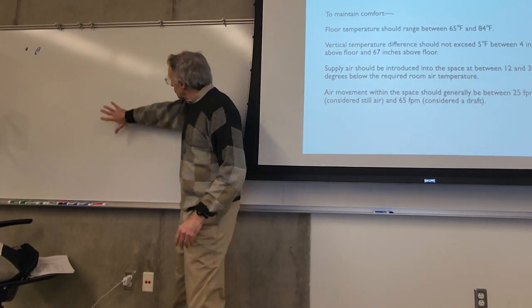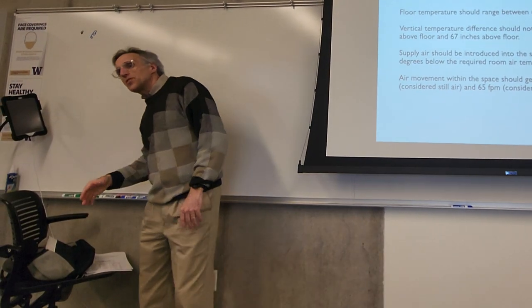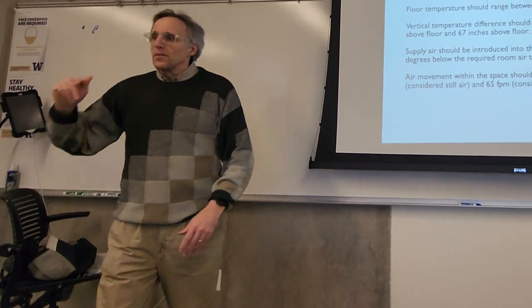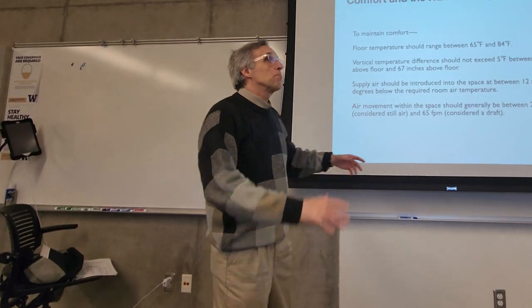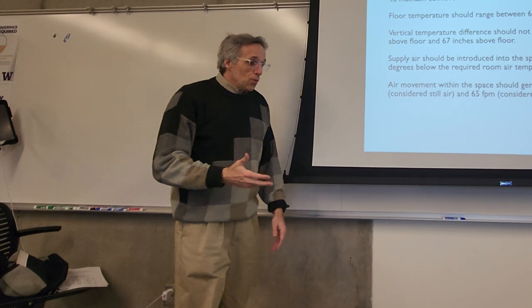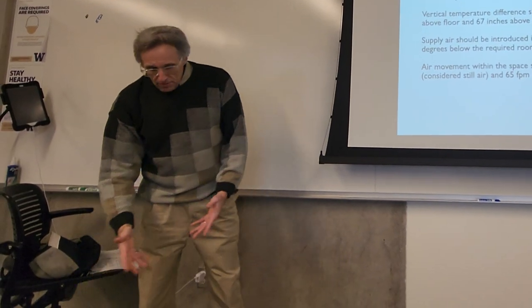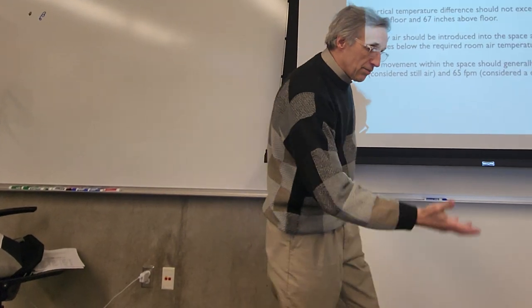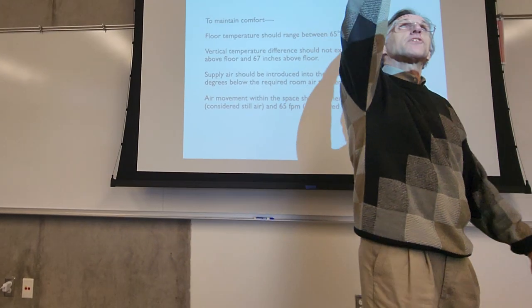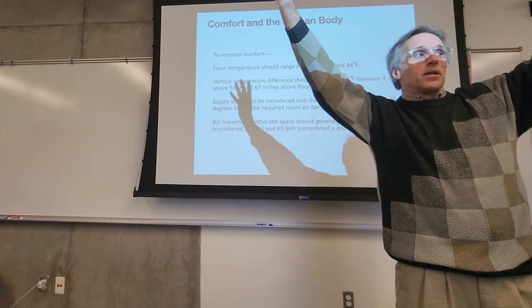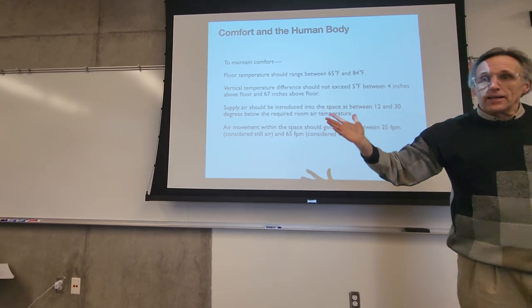You don't put registers right there, because if I'm standing here, it's like, oh man, it's hot, it's cold. So you put them up. Ideally, you want to have heating vents, you want to have warm air coming out of the floor, right? Not warm air coming out of the ceiling, because warm air rises. It's a nice way to heat the ceiling. But sometimes it has to be that way.